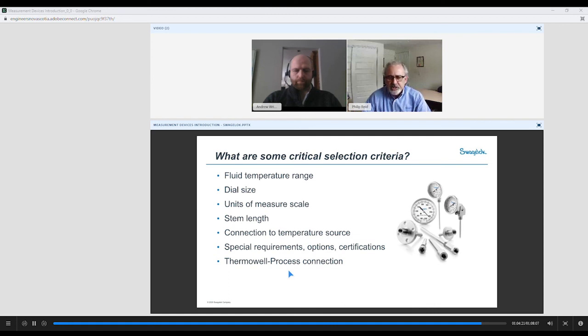And a few things you need to know when selecting a thermometer. Once again, you're going to need to know the fluid temperature range, the dial size that you're looking for, the units of measure and the scale, the stem length, the connection to the temperature source. Any special requirements, again, we talk about options such as material traceability, certificates of conformance, accuracy, those types of things. And are you going to use a thermowell as the process connection?